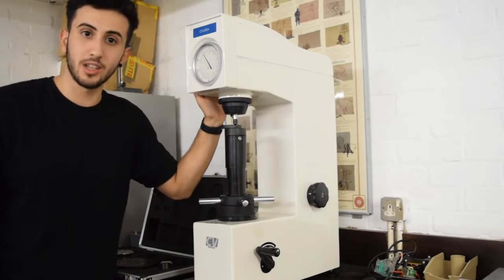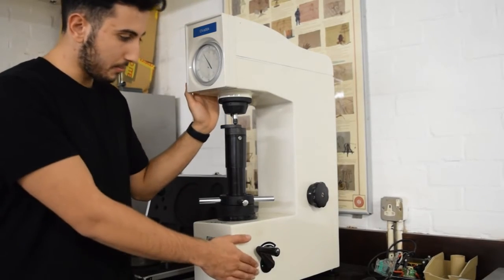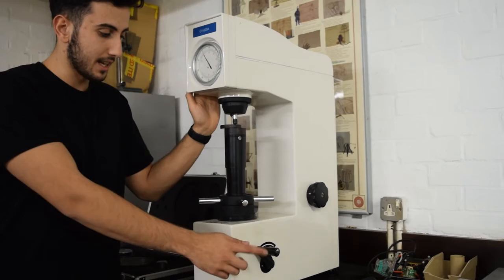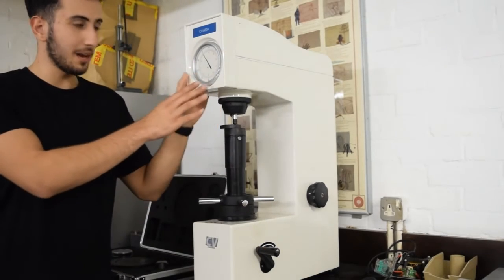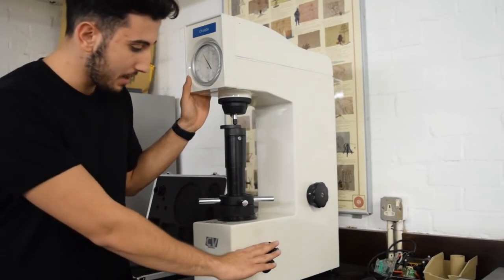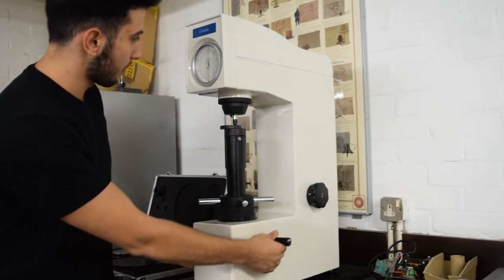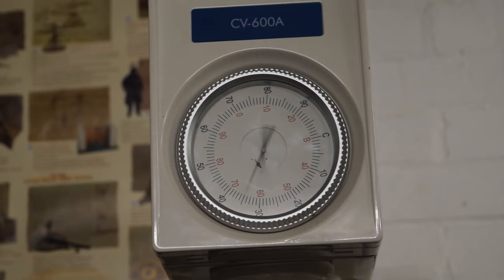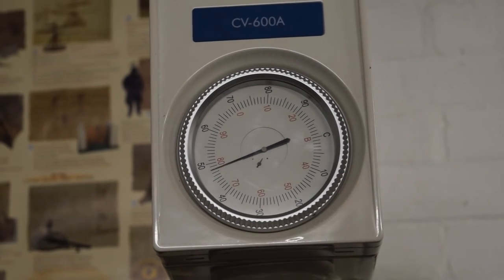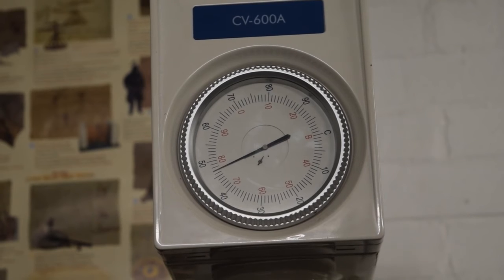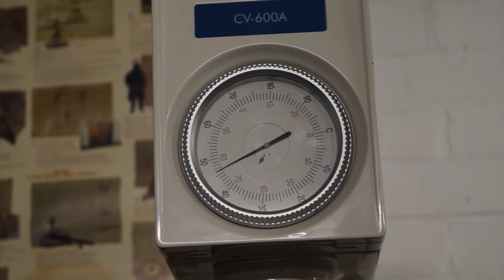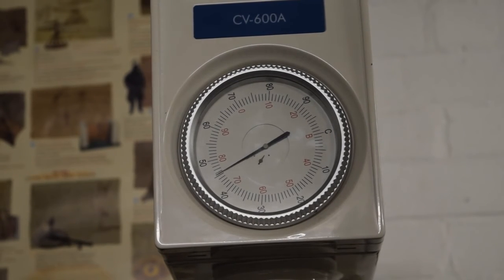This machine is hydraulically controlled, so it's got the major load configuration setting here. So once you've applied and calibrated the dials, you can apply the major load by simply just pushing it down. Then you wait for the needle to settle. And release the load.